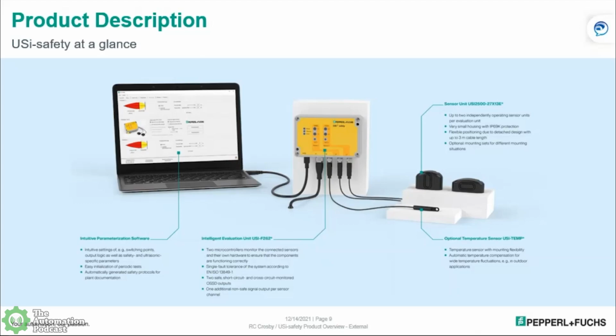The other part of this, as you see on the laptop on the screen, is the programming software. It's very easy, very intuitive. Once you've set your parameters, you release the sensor to the safety application, and then it will generate the paperwork you need to put with your risk assessment at the machine. So it will help provide the safety documentation for your application.